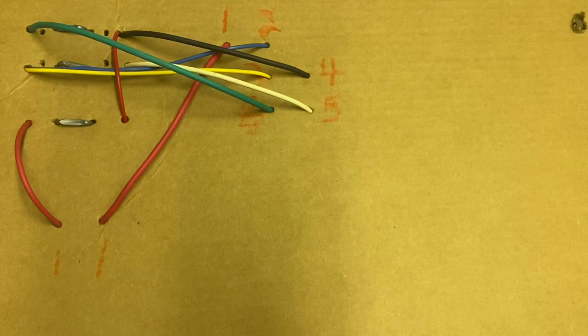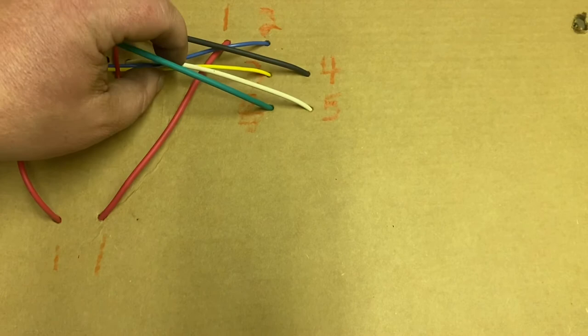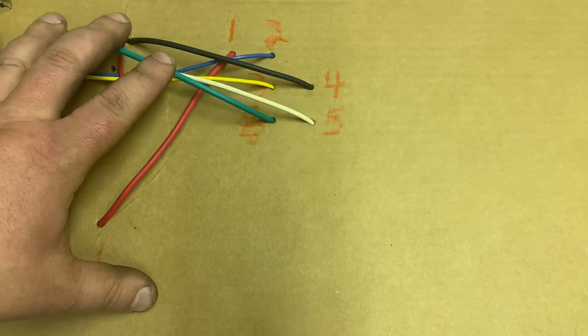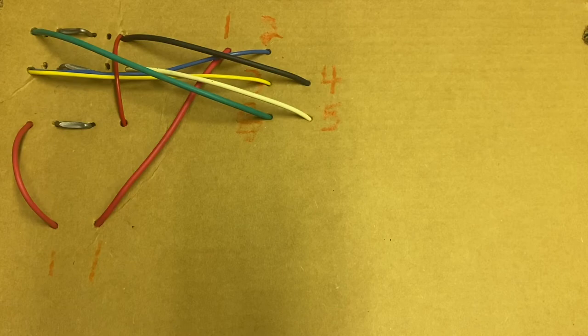Okay, so now when we flip it the other way, the power is going this way. So power is going to four and eight, and now five is back where it needs to be with two and three. So that's all we have to do. So we know between our motor and our switch we need to run one, two, three, four, five, and that's green. That's green doesn't mean ground, I'll be separate wire of course. So one, two, three, four, five, six, plus a ground. So we need, no, we need to run seven wires between our motor and our switch to get this going.